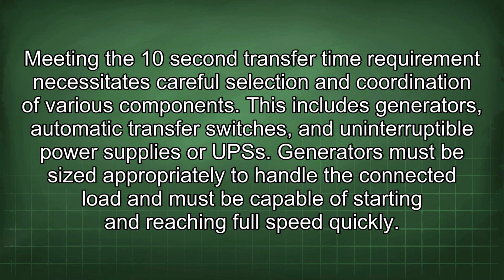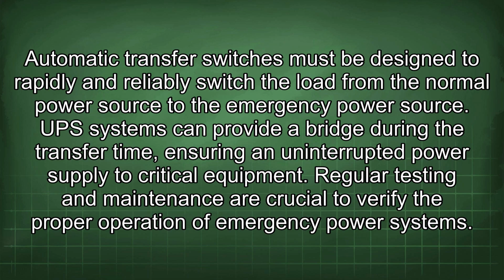Meeting the 10-second transfer time requirement necessitates careful selection and coordination of various components. This includes generators, automatic transfer switches, and uninterruptible power supplies, or UPS. Generators must be sized appropriately to handle the connected load and must be capable of starting and reaching full speed quickly. Automatic transfer switches must be designed to rapidly and reliably switch the load from the normal power source to the emergency power source. UPS systems can provide a bridge during the transfer time, ensuring an uninterrupted power supply to critical equipment.